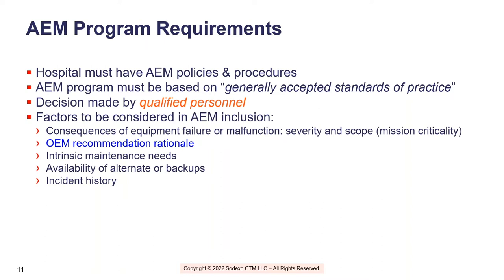So factors we're looking at: consequence of a failure. Again, if you only have one of these devices, or if this device affects multiple service lines. An ICU monitor isn't that critical in the grand scheme of things, we've got replacement ICU monitors, but if that central station goes down, it affects a much broader swath. So OEM recommendations, the rationale, intrinsic maintenance needs, availability of backups—infusion pumps, you've got plenty of those most of the time.